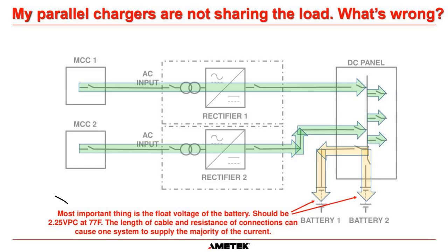But this phrase down here at the bottom is very important. The most important thing on any DC system is the float voltage of the battery. Really, the voltage of the system is designed to keep your batteries charged at the best voltage, so losses and heat aren't caused. And as electrical people, we should understand if this cable here is shorter than this cable here, then we're going to have a different volt drop on this top cable compared to this cable here. So let's say you set this voltage at 135 volts and this voltage at 135 volts, and let's say, just for ease, the voltage drop of this cable is 0.5 volts, and we'll say the voltage drop of this cable is 1 volt.